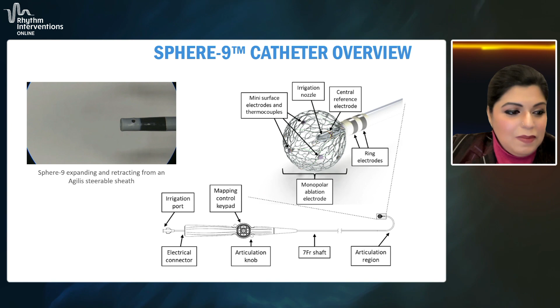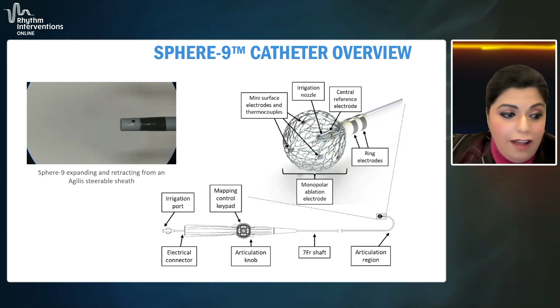The catheter is a 7 French bidirectional deflectable catheter. It has an expandable 9mm nitinol lattice electrode that has 9 mini electrodes, and the 9 mini electrodes sit on the spherical surface. The lattice tip contains a central indifferent electrode that does not come in contact with the tissue, and 2 additional ring electrodes that are located proximally on the shaft.